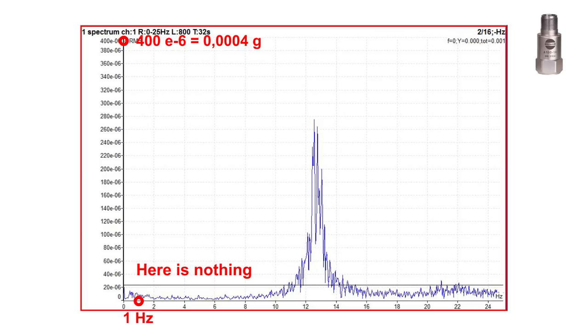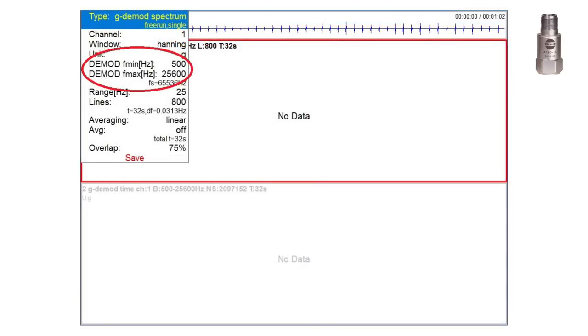Demodulated spectrum can display something visible. The demodulation spectrum uses the time signal which is enveloped. You can see the demod bandpass parameters. We want to measure only in band from 500 Hz to 25 kHz. We are not interested in low frequencies.